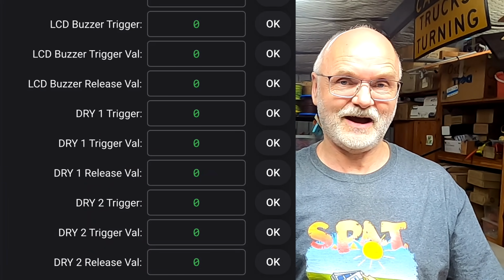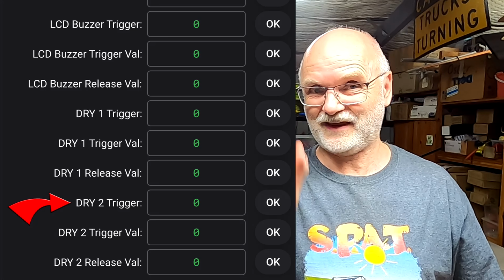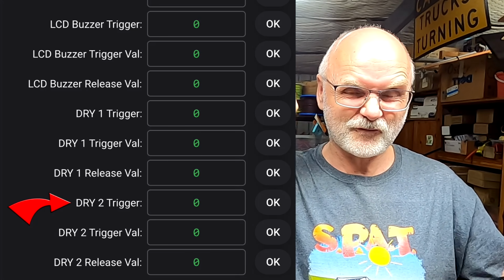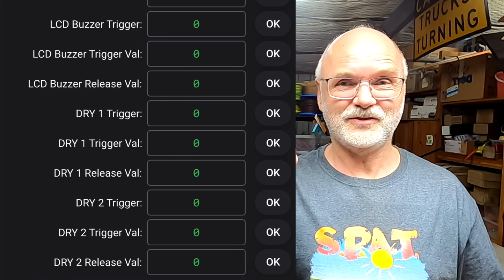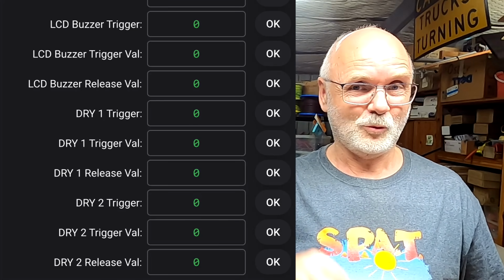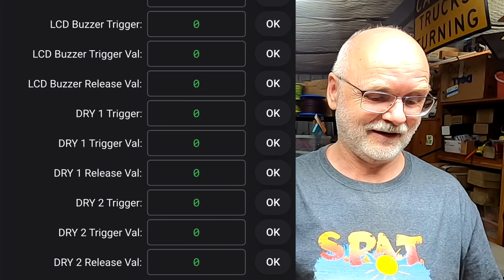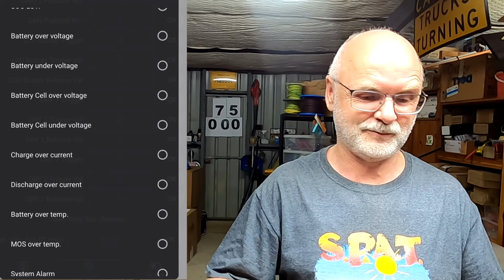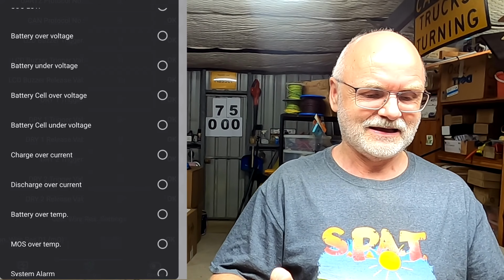Your guess is absolutely right—below that is a dry 2 trigger, for the second contactor. So we can now freely program these two relays, when they trigger and when they release again. A lot of parameters for a lot of trigger points: voltage, current, temperatures, alarms.